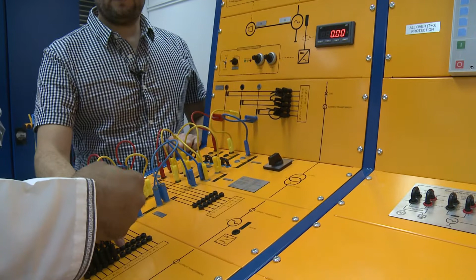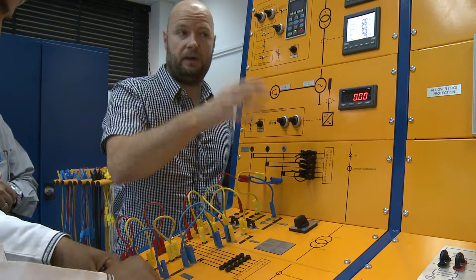I have a question - why did you add a protection to that one and not to this one? This one is a complete system, and this one's more of an additional system. It could be purchased with the same relays, with an extra relay, but you don't really win any more functionality. In this one we can already demonstrate this, so we don't need to - they're quite expensive, and we have an online tap changer. This has just continued for the last 10 to 15 years. If you want to demonstrate taps, then you can use this.